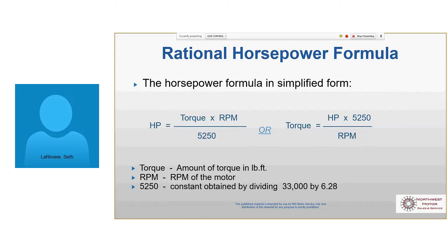There's a simple little shortcut. If you're using an 1800 RPM motor, the horsepower times 3 is your torque. So if it's a 5 horsepower motor, times 3, it produces 15 foot-pounds of torque. So for a 4-pole motor, it's 3 times the horsepower is your torque.